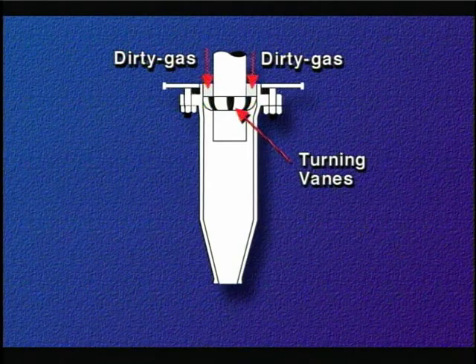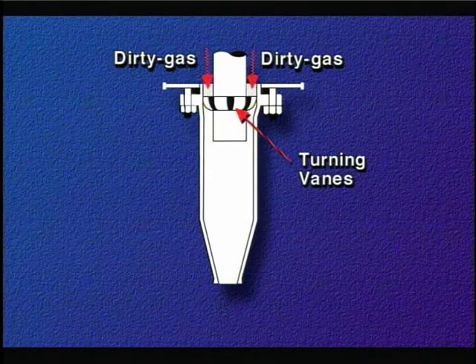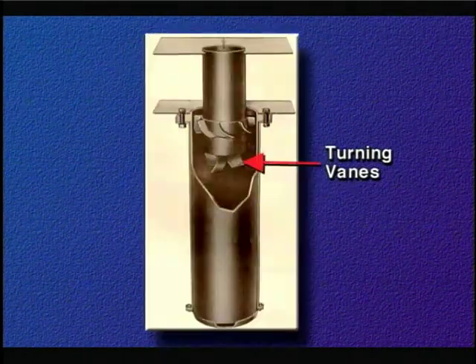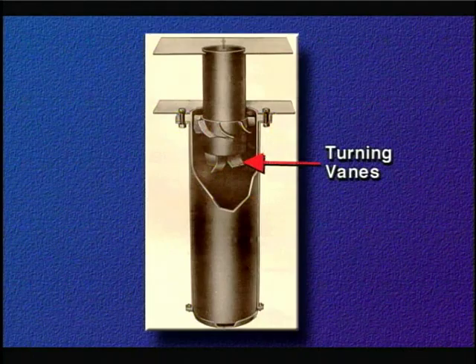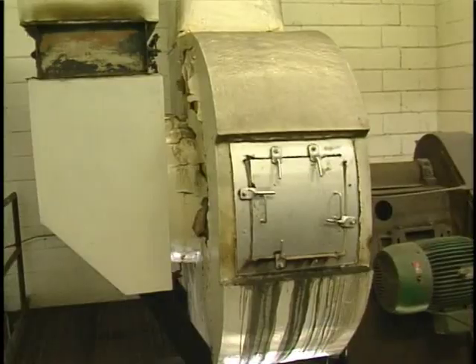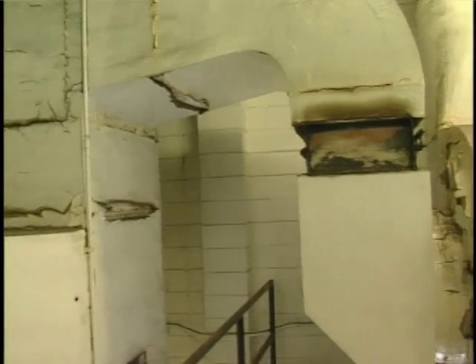Turning vanes are mounted in this annular space in order to impart rotation to the entering gas stream. In some designs, turning vanes are also mounted at the entrance of the exit pipe. As with the larger diameter cyclones, the exit pipes extend into the upper body of the cyclone to prevent direct discharge of the entering gases.